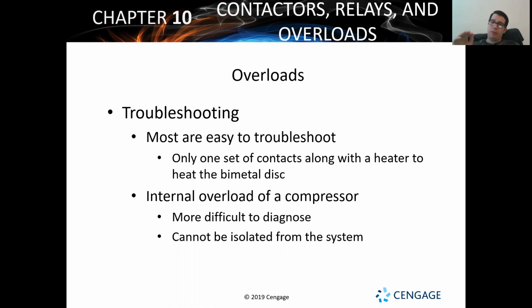That's all it takes. But an internal overload on a compressor is in series in the windings inside of that compressor. You cannot get to that component by itself. The one thing you've got to let it do is cool off. All right. This is the way that you can have the internal overload deactivating and closing contacts again, allowing that winding to be completed.